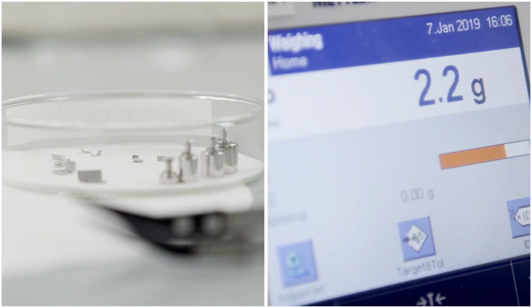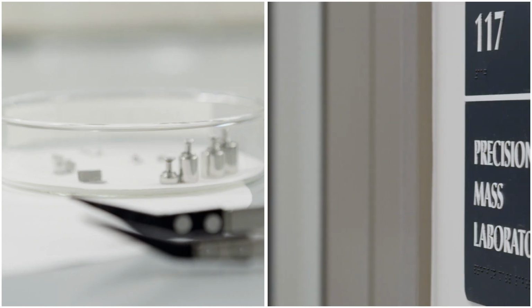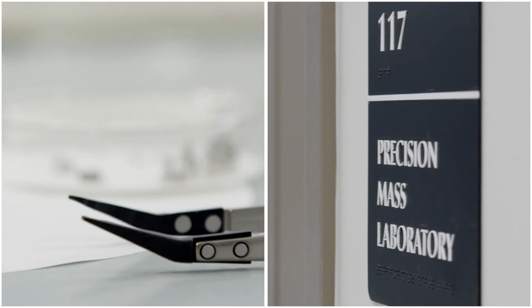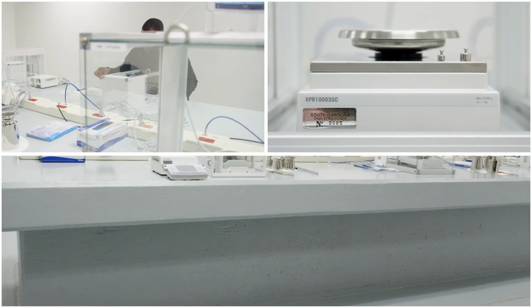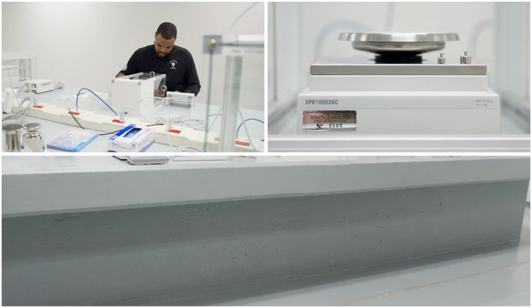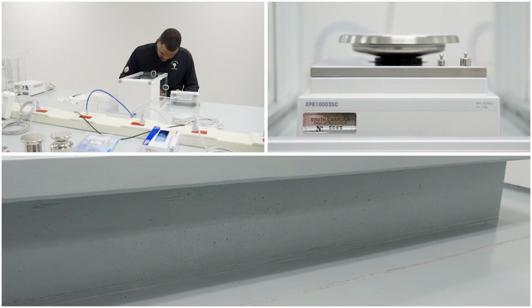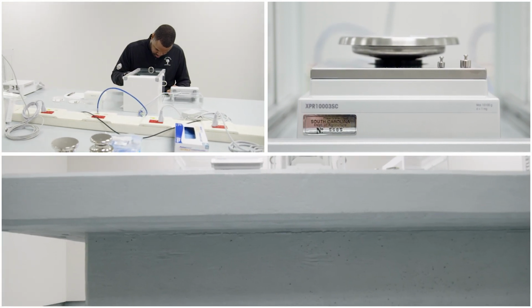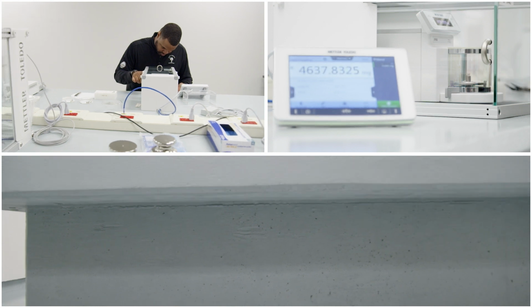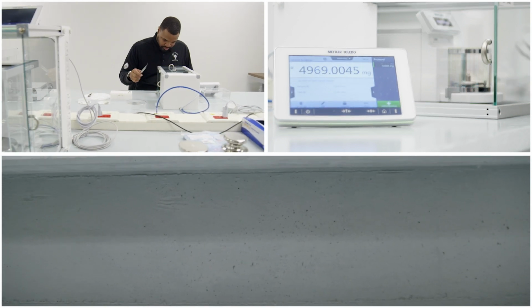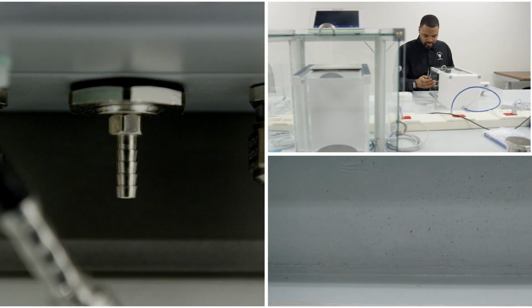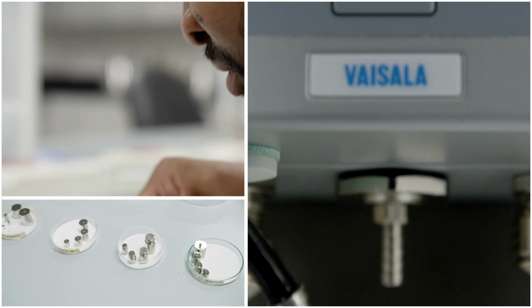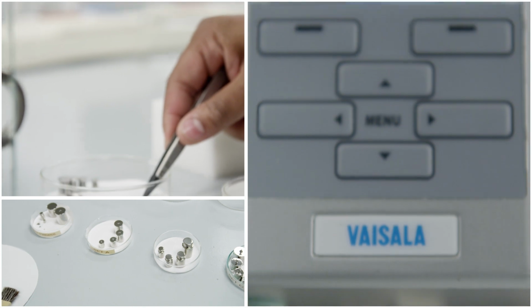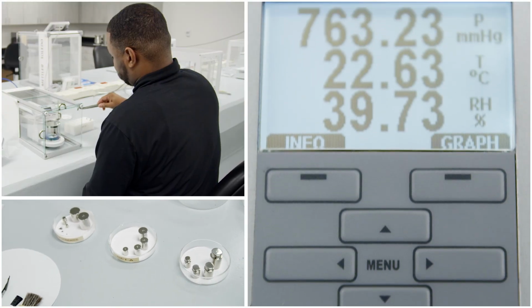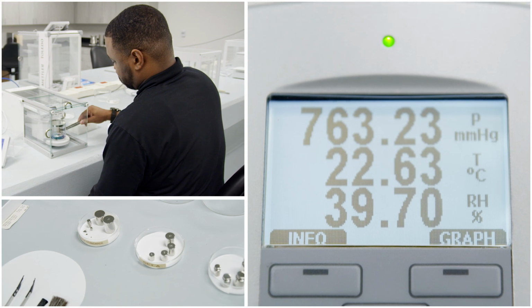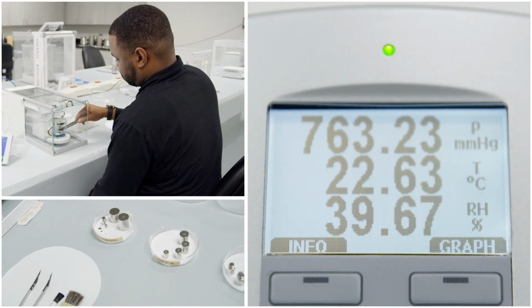So, to maintain ultra-precise measurements, this lab was built to accommodate for the rotation and vibration of the Earth. For example, this is an inertia table. Underneath is 12 feet of solid concrete that is isolated from the building and interwoven with rebar made of fiberglass to eliminate static electricity. The paint is high-grade epoxy and is electrostatic resistant. And even the temperature and humidity in this room are controlled to 1 degree Celsius and 0.2% relative humidity. After all, when you're calibrating weights the size of your eyelash, every minute detail matters.